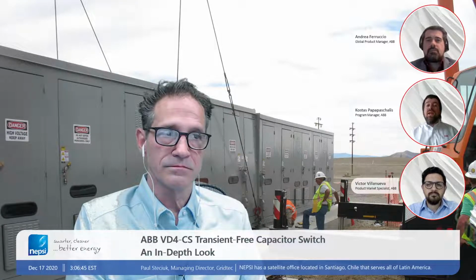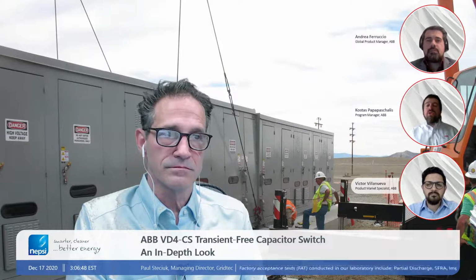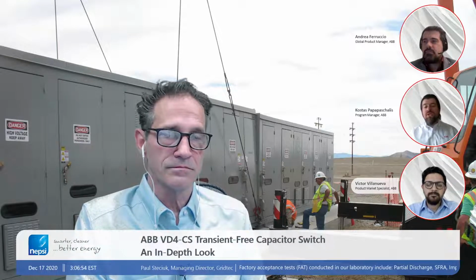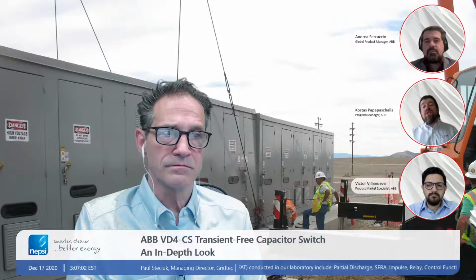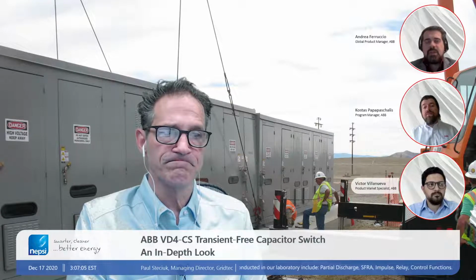Andrea, I would call also a redundant system the fact that the VD4-CS is also a breaker. So you don't really need an input of the voltage sensor in order to open and operate. So in case you have an issue on the sensor and you see no voltage, or you see voltage that has strange values, the VD4-CS will be able to operate and clear the fault, or put your system in a safety condition, and then you can, of course, go see what's wrong with the sensor, what's wrong with the other components. So we definitely have this redundant operation, but clearly, if you don't have a sensor, you cannot expect to have synchronization and normal operation there. That's correct.